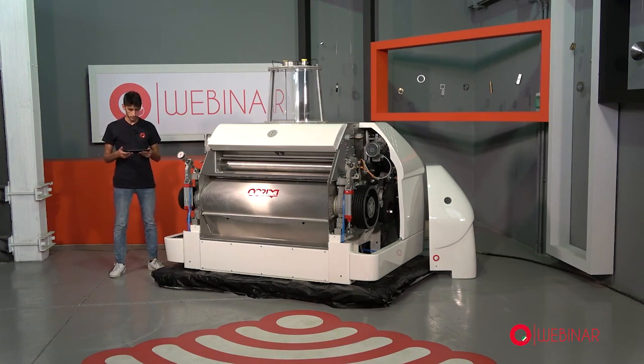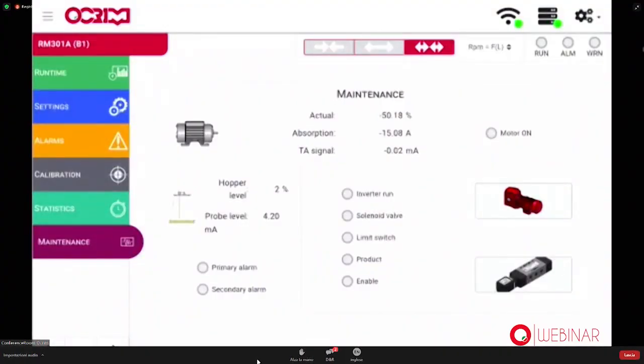Then the maintenance page is useful, especially for technicians that want to analyze the functioning of the machine. In fact, we can see different kinds of data, for example, the absorption of the motor that we could see even in the runtime page, but there's also the electric signal, the 4-20 milliampere signal of the transformer, which measures the absorption of the milling motor. The same happens with the level probe. On top of the percentage, we can also see the analog signal that the controller on board of the machine receives. In this case, we're talking about a 4-20 milliampere signal. We have information about the state of the machine, so if we have a primary or secondary alarm, and other kinds of information like the presence of the product or authorizations, sensor state, etc. Now we can move on to the test phase.